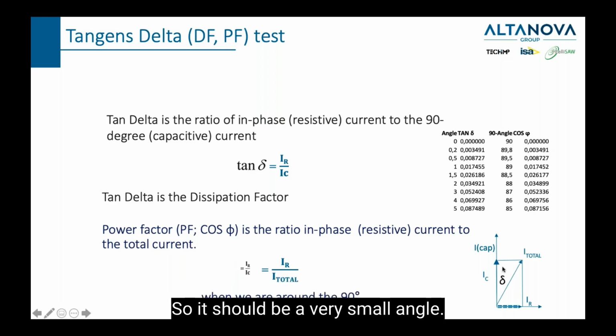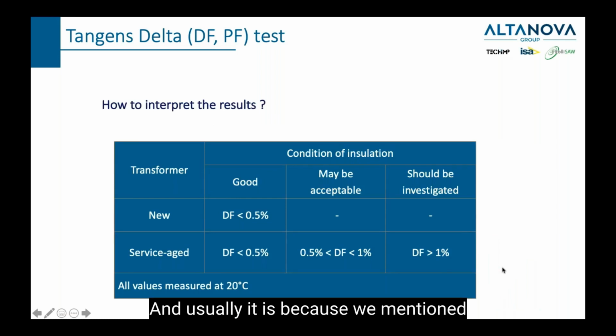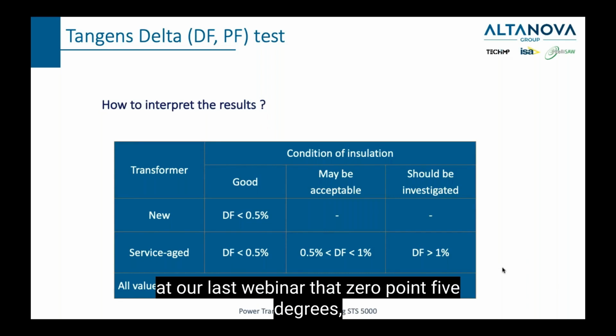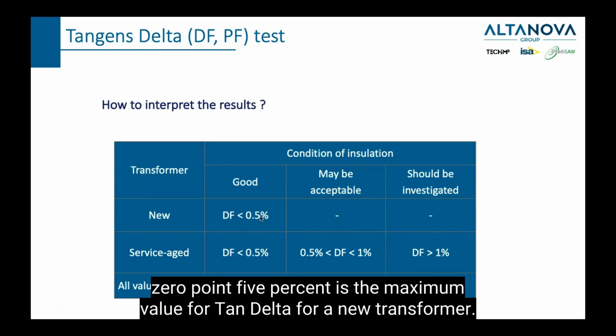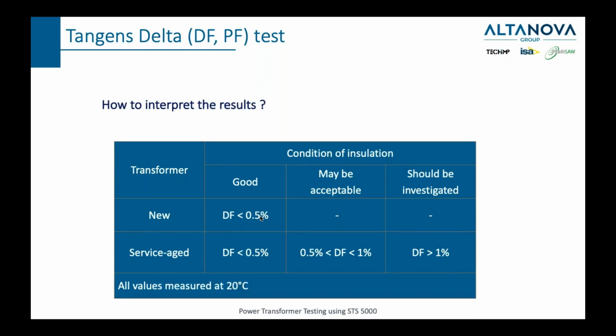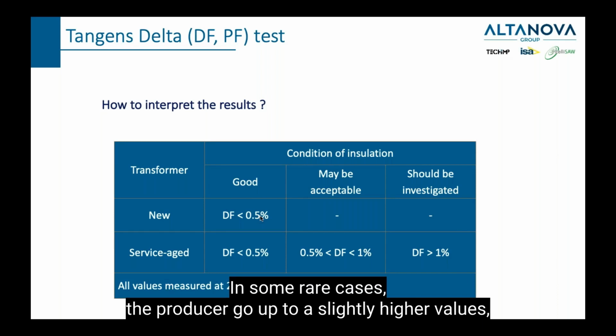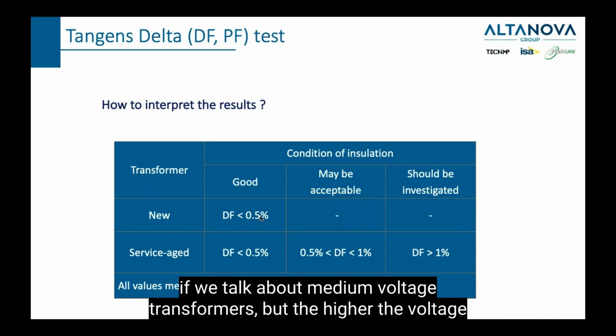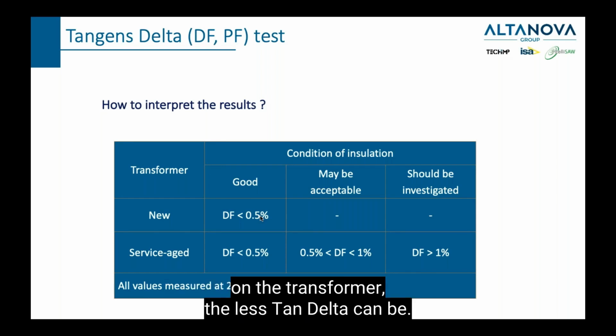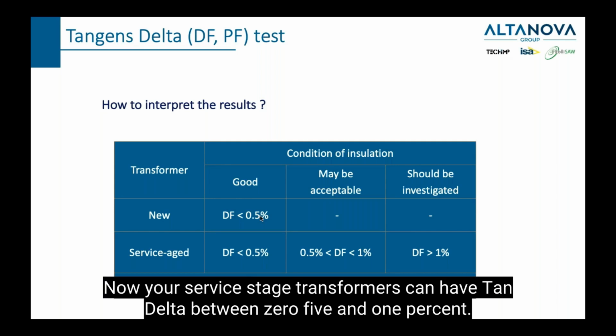So it should be a very small angle, and usually it is, because we mentioned at our last webinar that 0.5%is the maximum value for tan delta for a new transformer. In some rare cases, producers go up to slightly higher values if we talk about medium voltage transformers, but the higher the voltage on the transformer, the lower tan delta can be. Now, your service aged transformers can have tan delta between 0.5 and 1%.